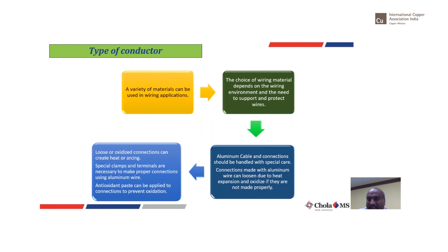All those things play a major role in ensuring that the cables have a better and proper life. Loose or oxidized connections can in turn lead to heating and arcing, and this arcing can in turn lead to a break. And if this is for a neutral or a grounding, then it can be much more devastating. An earthing wire getting cut can be more dangerous.